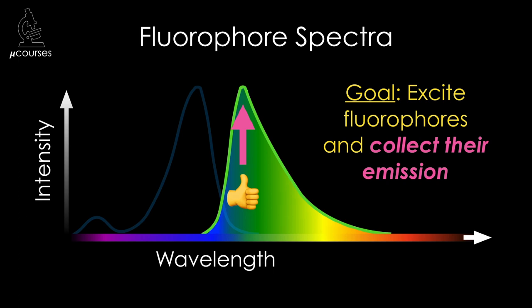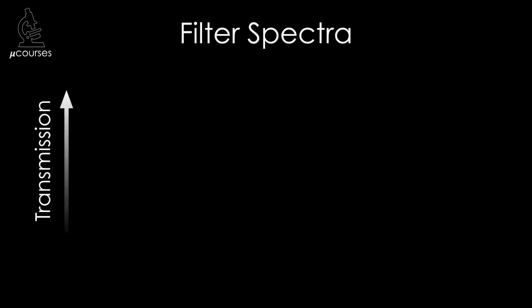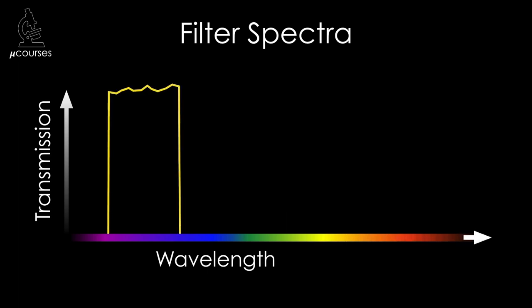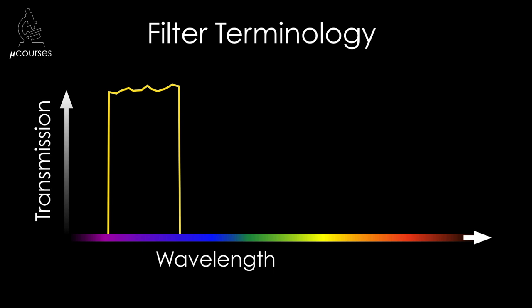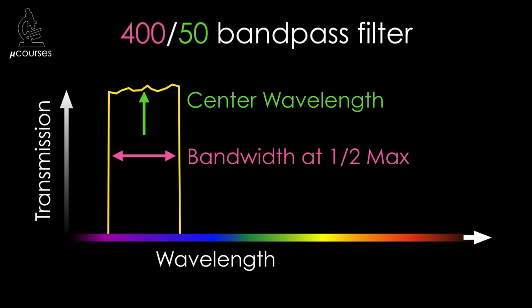We're going to select for excitation and emission wavelengths using filters. Filters are optical elements designed to block some wavelengths while transmitting others. The blocking and transmission properties of filters can be visualized on spectra. The center wavelength tells us where along the spectrum the filter transmits, and the bandwidth at half-maximal transmission tells us the range of wavelengths transmitted. These numbers are written as center wavelength slash bandwidth — for example, a 400/50 nanometer bandpass filter.